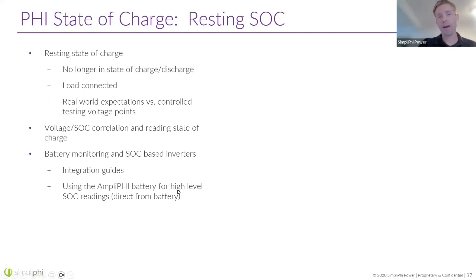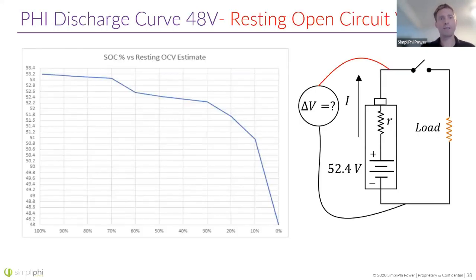And the AmpliPhi battery and the SimpliPhi battery, with their advanced BMS units and their closed-loop communications, can provide a lot of information and very accurate high-level state of charge readings at the battery level, meaning you can get them from all individual batteries with monitoring. So here's an example of a 48-volt battery. When it's 100% state of charge, we're looking at actually above 53 volts, so 53.2 volts. This depends a little bit on temperature, and these measurements are at room temperature, 25 Celsius.